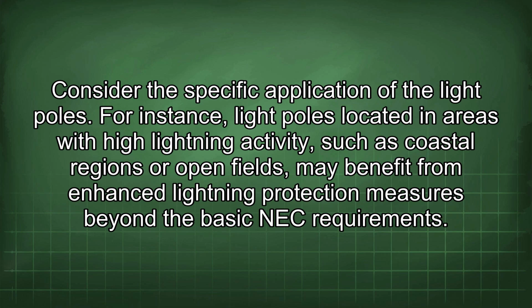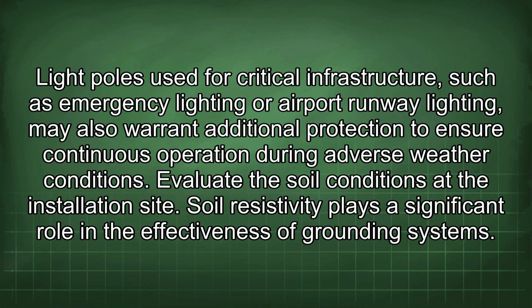For instance, light poles located in areas with high lightning activity, such as coastal regions or open fields, may benefit from enhanced lightning protection measures beyond the basic NEC requirements. Light poles used for critical infrastructure, such as emergency lighting or airport runway lighting, may also warrant additional protection to ensure continuous operation during adverse weather conditions.